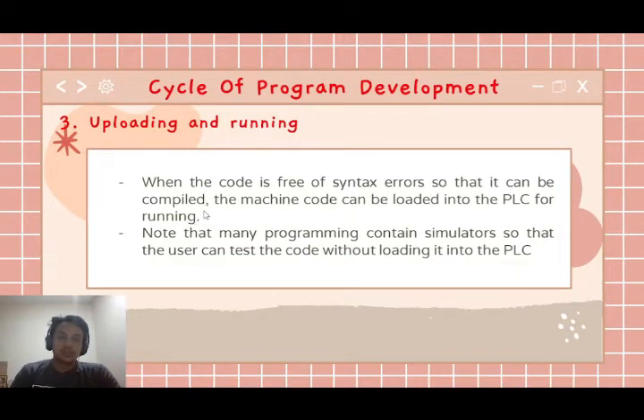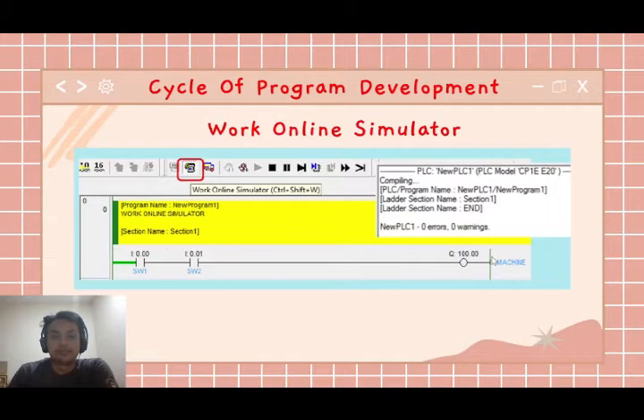Number 3 is uploading and running. When the code is free of syntax errors so that it can be compiled, the machine code can be loaded into the PLC for running. Note that many programming tools contain simulators so that the user can test the code without loading it into the PLC. This is Work Online Simulator. We can see this icon. When we click this icon, the online simulator will run. Then we can know by this table, 0 errors and 0 warnings, that the programmer's ladder diagram is correct.